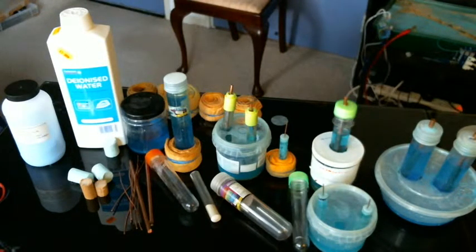A half cell cannot be calibrated. That is why it is used as a reference potential in laboratory tests. A reference cell can be checked against another reference cell in closed circuit condition, but it cannot be altered or calibrated to make it more capable of use as a measuring instrument. It is not a measuring instrument.